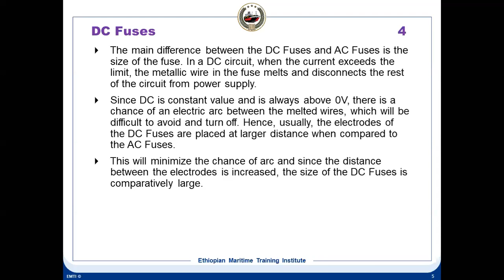That is the difference. The electrodes of the DC fuses are placed at a little larger distance when compared with the AC fuses. This will minimize the chances of arc. Since the distance between electrodes is increased, the size of the DC fuse is also comparatively large. So you have a DC fuse and you have an AC fuse, and in the DC fuse the electrodes inside are placed at a little larger distance.